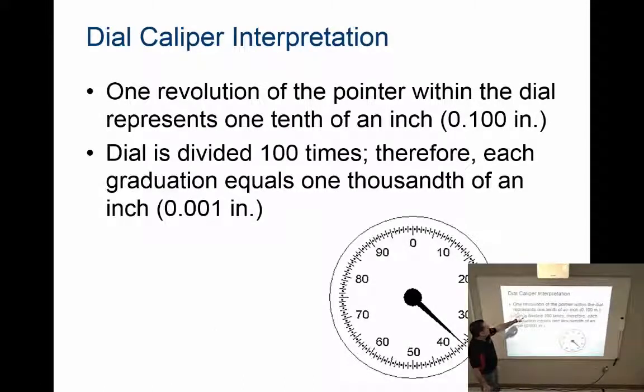One revolution of the pointer within the dial represents one tenth of an inch. The dial is divided a hundred times; therefore, each graduation equals one thousandth of an inch. The small dots between lines are five ten-thousandths of an inch, even smaller than that.